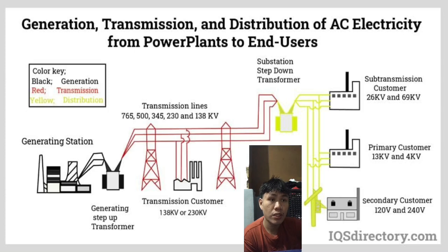As shown in the image, electricity enters a step-down transformer at the substation. Here, the voltage is reduced from transmission level to subtransmission or primary distribution levels, such as 69 kilovolts or 26 kilovolts. In Tacloban City, LEECO operates and manages these substations, which serve as control centers where electricity is monitored, protected, and prepared for distribution. Without these substations, electricity would be too dangerous and impractical to deliver to homes, schools, hospitals, and businesses.